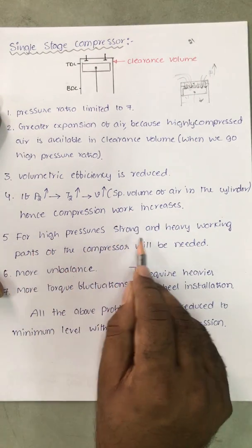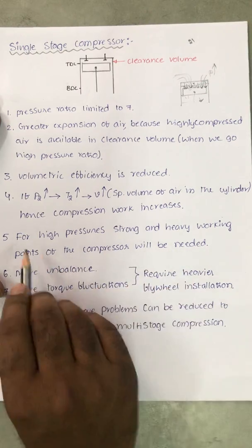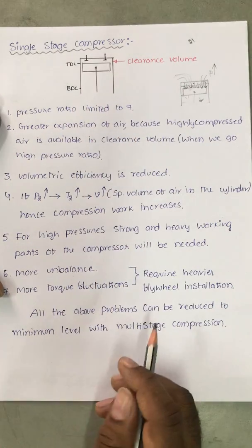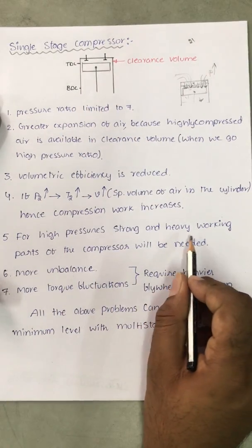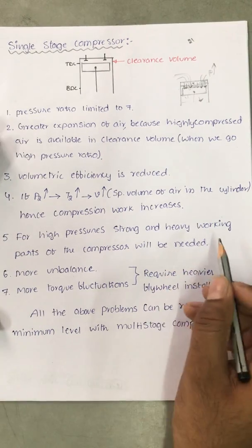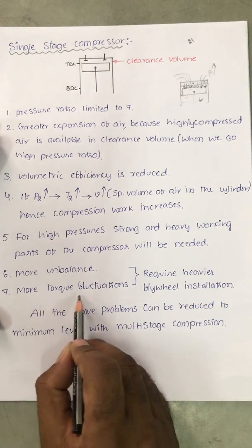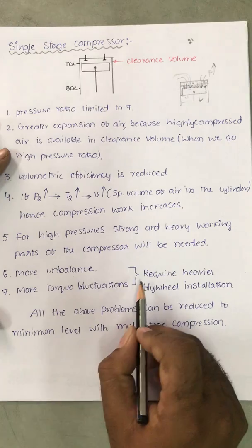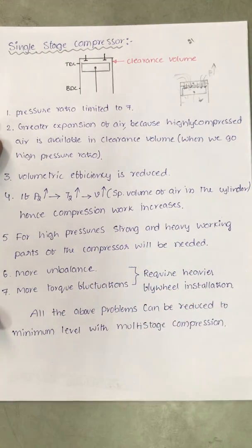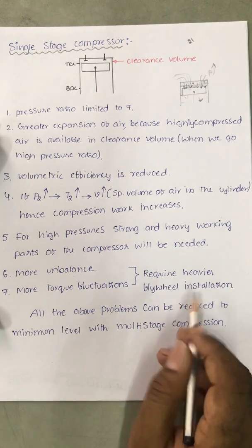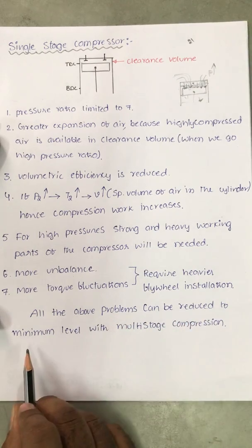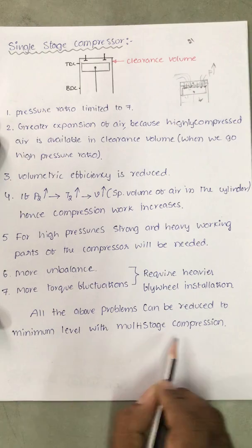For high pressures with only one cylinder, strong and heavy working parts are needed — the crankshaft, piston, and connecting rod all need to be very strong and heavy. Large parts cause more imbalance and more torque fluctuations. To balance these, a heavier flywheel installation is required. All these problems can be reduced to a minimum with multistage compression.